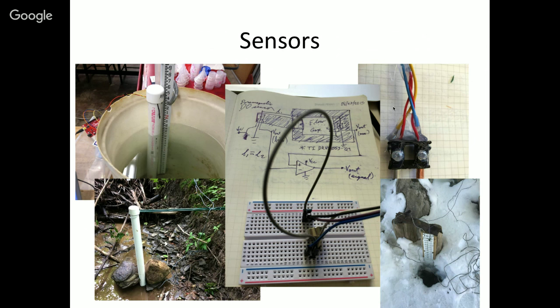Both are magnetic field sensors, based on the idea that dissolved oxygen modifies the magnetic field in water. So we've got two magnetic field sensors with a magnet in the middle between them. As you can see in the diagram behind it, there's a gap between one of those and the other, and the other one has just a piece of plastic or something paramagnetic rather than ferromagnetic, sitting between that sensor and one side of the magnet. So we're able to measure the difference between those two Hall effect sensors' signals, which should be proportional to the amount of dissolved oxygen moving through that flow gap.